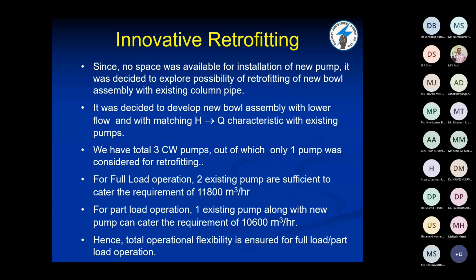So we have a total of 3 cooling water pumps, out of which only 1 pump was considered for retrofitting. The other 2 pumps will remain of the same capacity, and 1 pump will be refitted for reduced flow. Now for full load operation, 2 existing pumps are sufficient to cater to the requirement, that is 11,800 meter cube. For part load, one existing pump along with the new pump can cater to the requirement of 10,600 meter cube. Hence, total operating flexibility is ensured for full and part load operation.